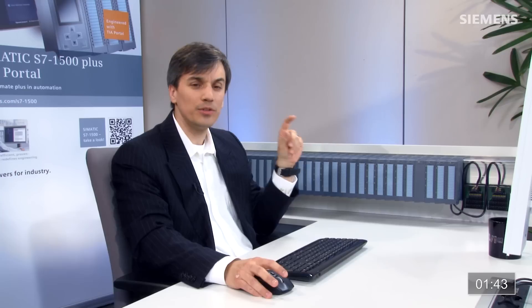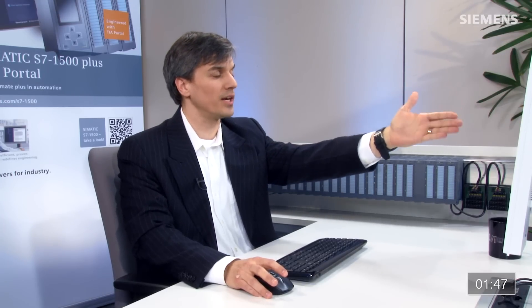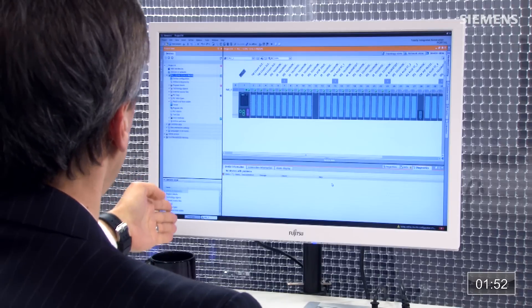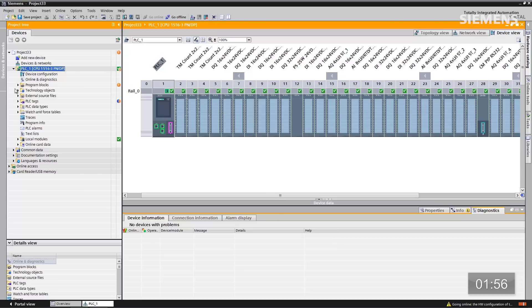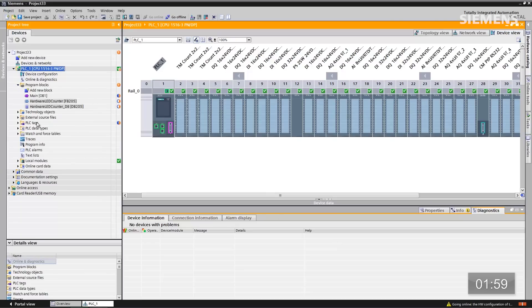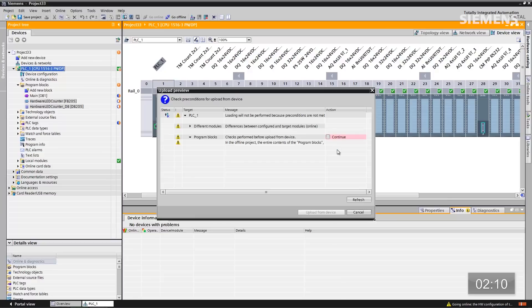Once it's found each individual module and the status of each one, it's going to start to populate with little checkboxes all the way across the entire hardware configuration, and at the exact same time, the code and the PLC tags. If I give focus to the program blocks, you'll see that I have a couple of blocks missing and something wrong with the tags as well. With focus on the CPU, I have an Upload button up top. I click on it, another dialog box pulls up asking if I want to continue — I say yes and click Upload from Device.